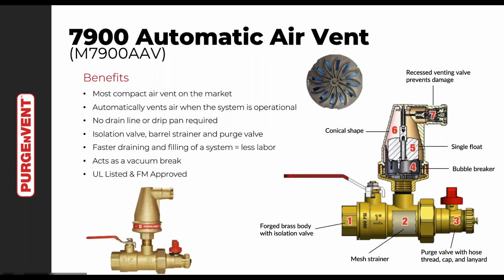The one that gets the most attention is actually the AGF model 7900 AAV, our automatic air vent, which is really a marriage of two valves. So we talk about the first valve at the bottom, 1, 2, 3. It incorporates a 1-inch full port isolation valve in case you ever have to service or inspect these units. It utilizes a barrel strainer, so the whole body of the valve is a strainer, so that protects the air vent mechanism located above it. And then we have the garden hose cap and chain purge valve. This allows you to flush out the strainer by NFPA 25 requirement. It also allows you to do a rapid air purge or rapid air inlet if you're draining systems very quickly.